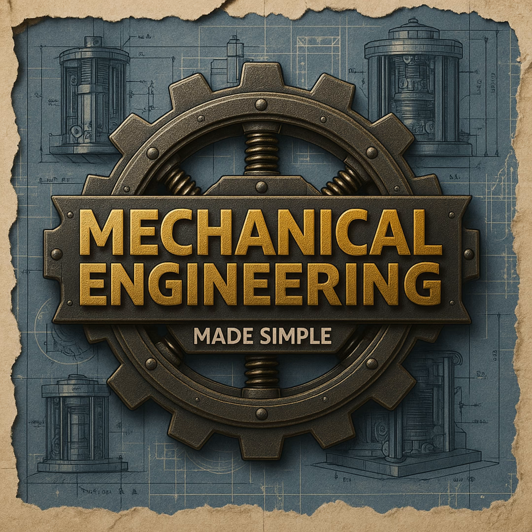The horsepower is calculated as P multiplied by GPM divided by 1714 times E, where E is the pump's efficiency. That looks like a bit of a mess of constants, but what's the quick takeaway for a designer? If I'm just starting to spec out a system, what's the rule of thumb? The quick approximation is incredibly useful, actually.